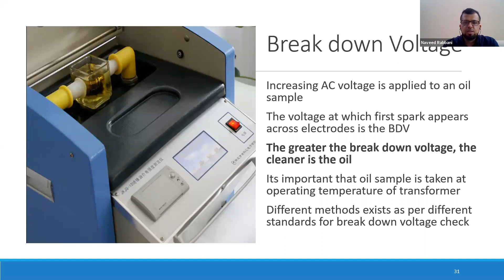On this slide, there are recommended values in light of the IEC 60422 standard of the oil quality parameters. Appearance: it should be clear and free from sediment and suspended particles. Color: maximum color must be 2. Breakdown voltage: here there are 3 columns.